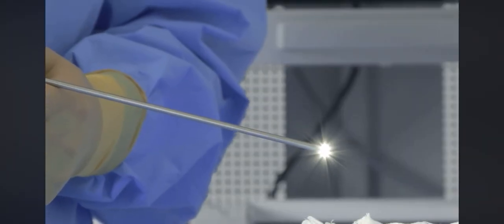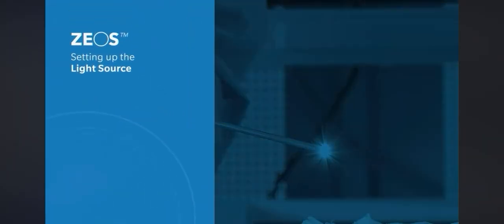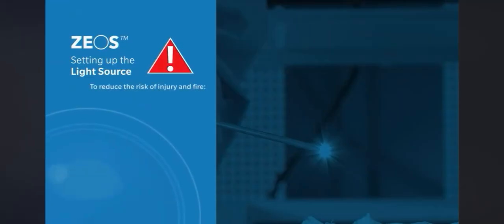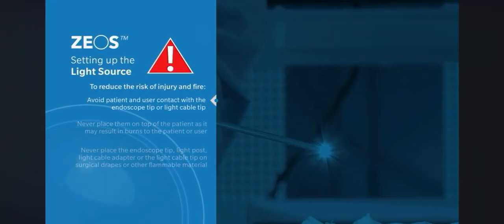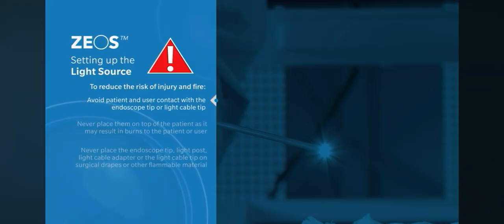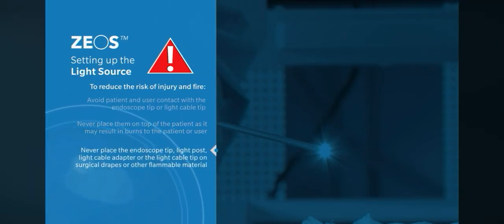When using the light source, it is important to understand the safety precautions. To reduce the risk of injury, avoid patient and user contact with the endoscope tip or light cable tip, and never place them on top of the patient, as doing so may result in burns to the patient or user. To reduce the risk of fire, never place the endoscope tip, the endoscope light post, the light cable adapter, or the light cable tip on the surgical drapes or other flammable material, as doing so may result in fire.